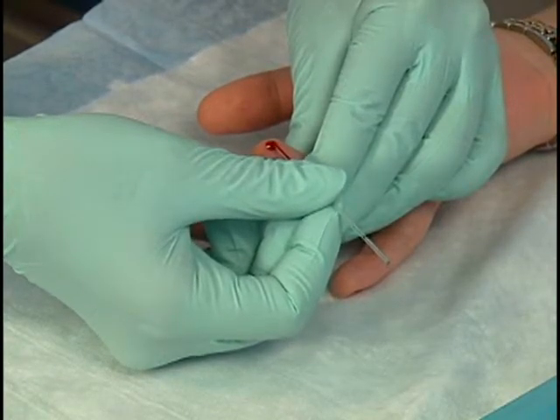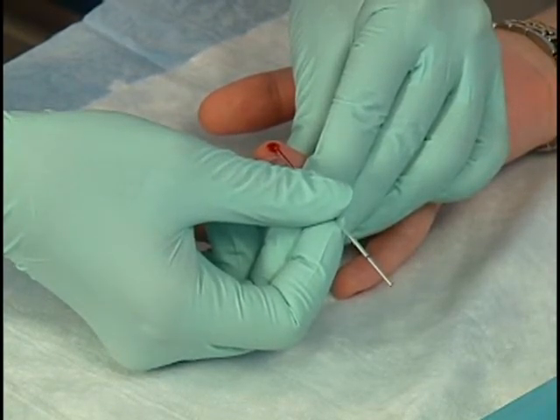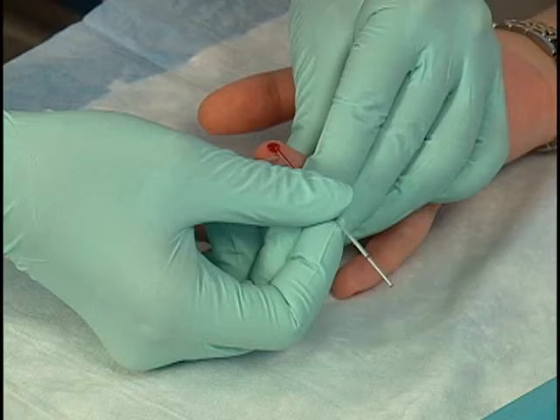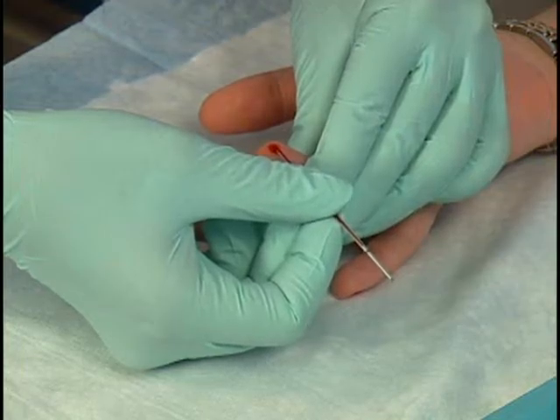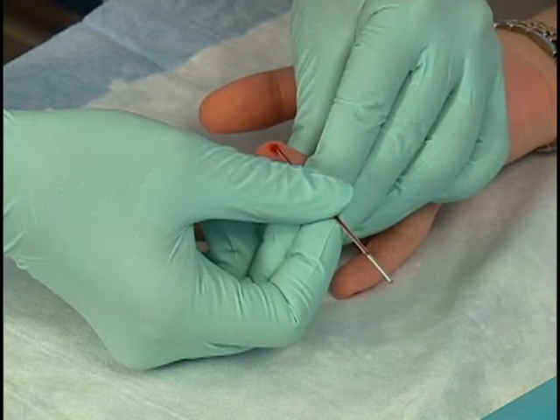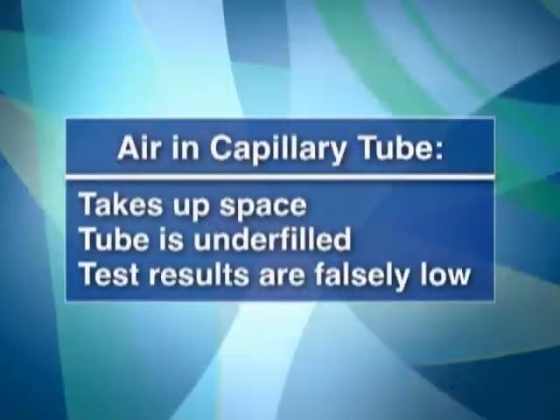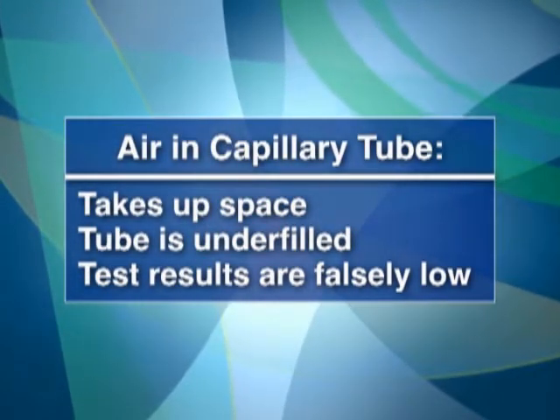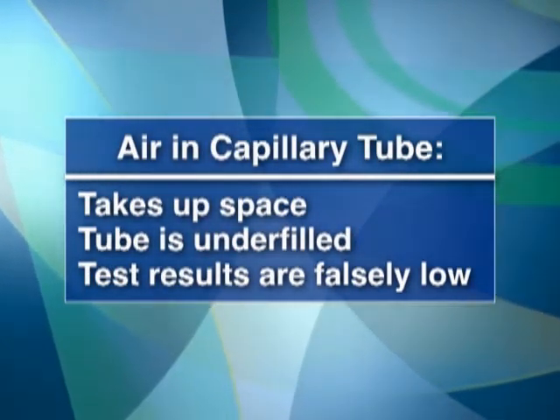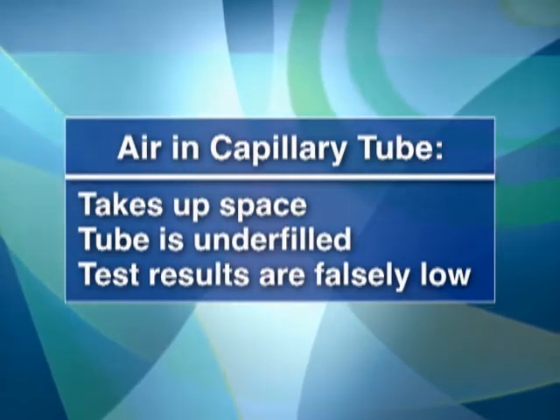As the blood starts entering the tube, you can slant the tube in a slightly downward position to facilitate blood flow into the tube. Fill the capillary tube to the black calibration line. Blood fills the tube through capillary action. Be sure to keep the tip of the capillary tube in the blood to prevent air from entering and causing inaccurate results. If an air bubble enters the tube, you must fill another tube. Air takes up space the blood should occupy, resulting in underfilling and falsely low test results.